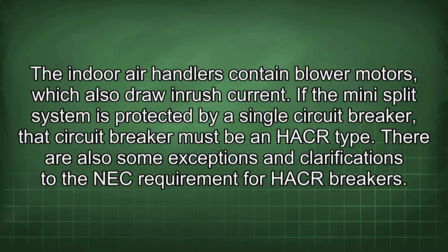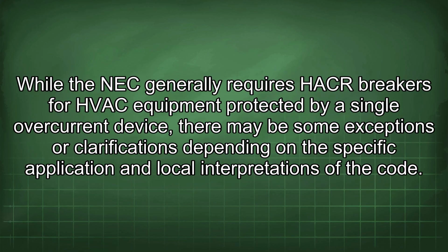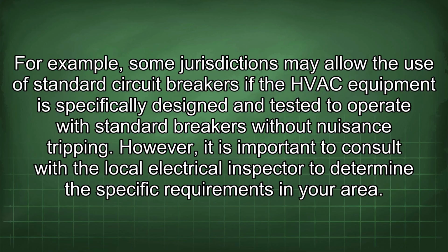There are also some exceptions and clarifications to the NEC requirement for HACR breakers. While the NEC generally requires HACR breakers for HVAC equipment protected by a single overcurrent device, there may be some exceptions or clarifications depending on the specific application and local interpretations of the code. For example, some jurisdictions may allow the use of standard circuit breakers if the HVAC equipment is specifically designed and tested to operate with standard breakers without nuisance tripping. However, it is important to consult with the local electrical inspector to determine the specific requirements in your area.